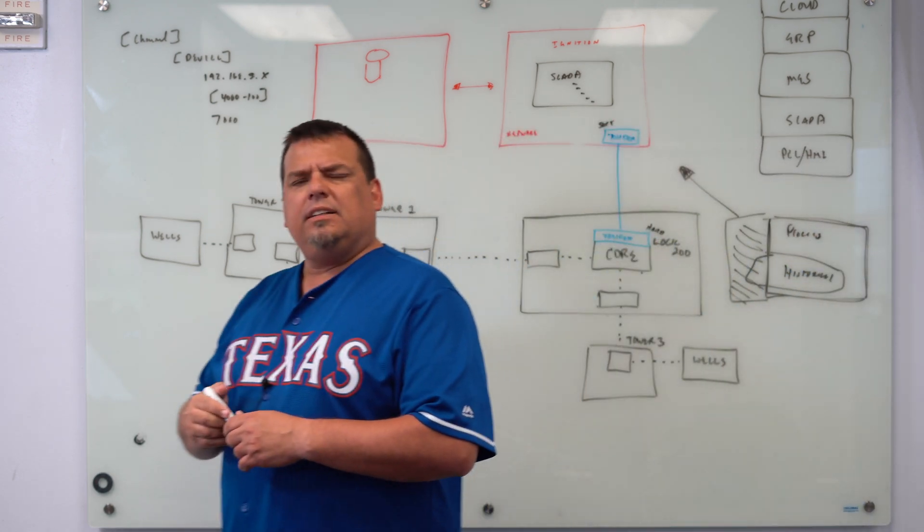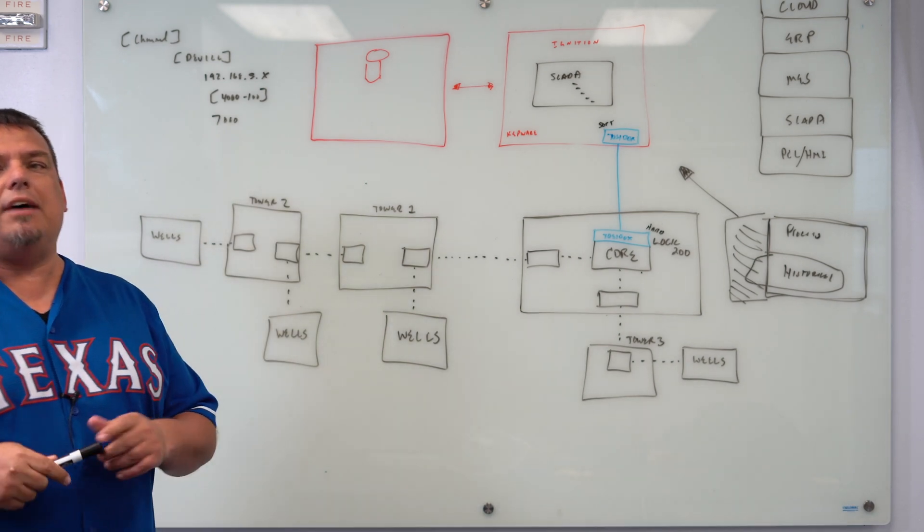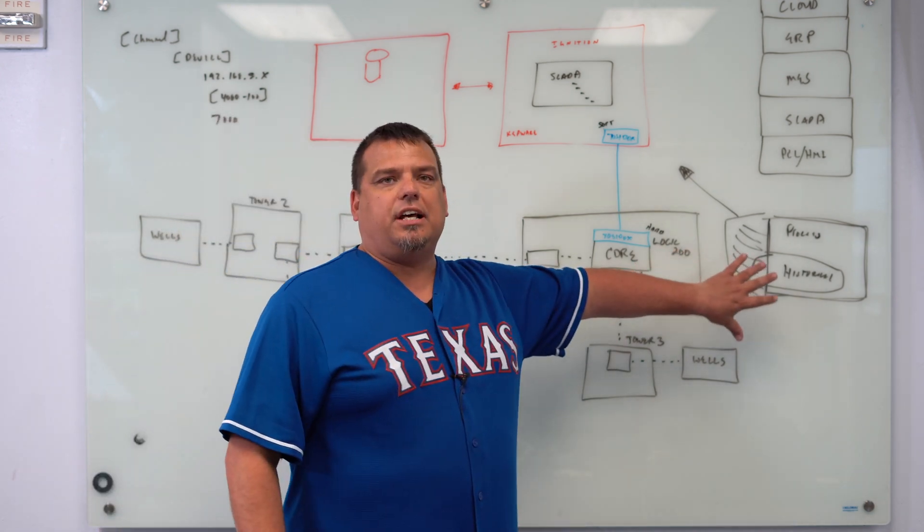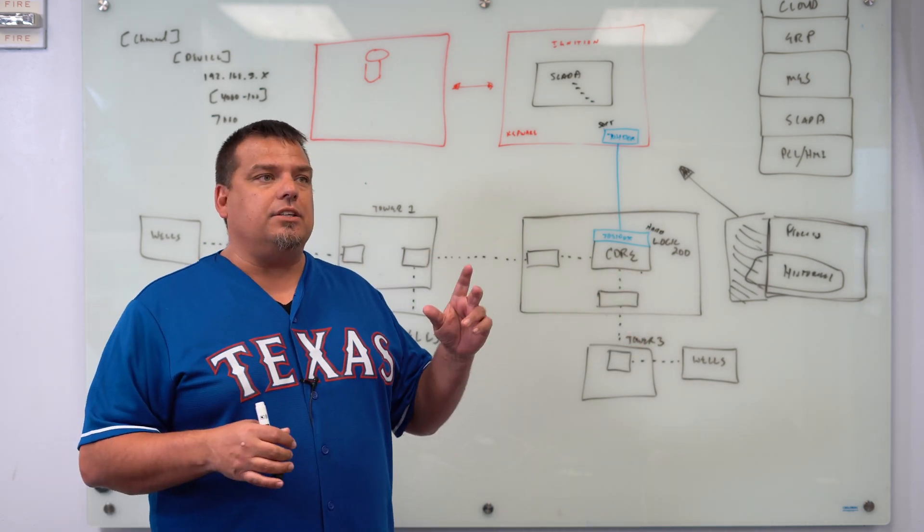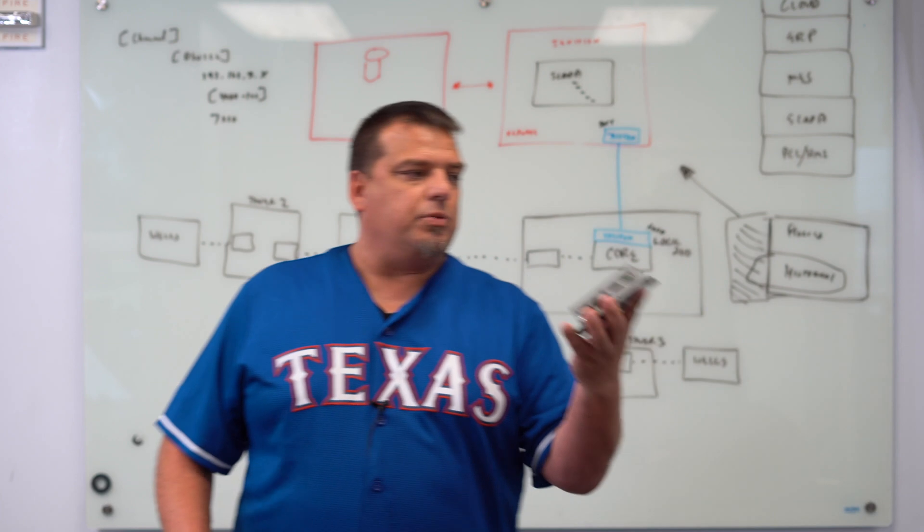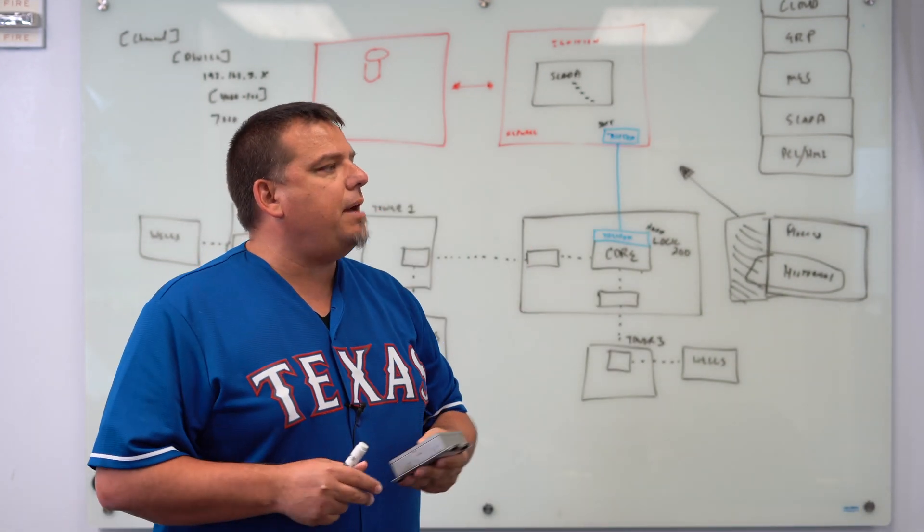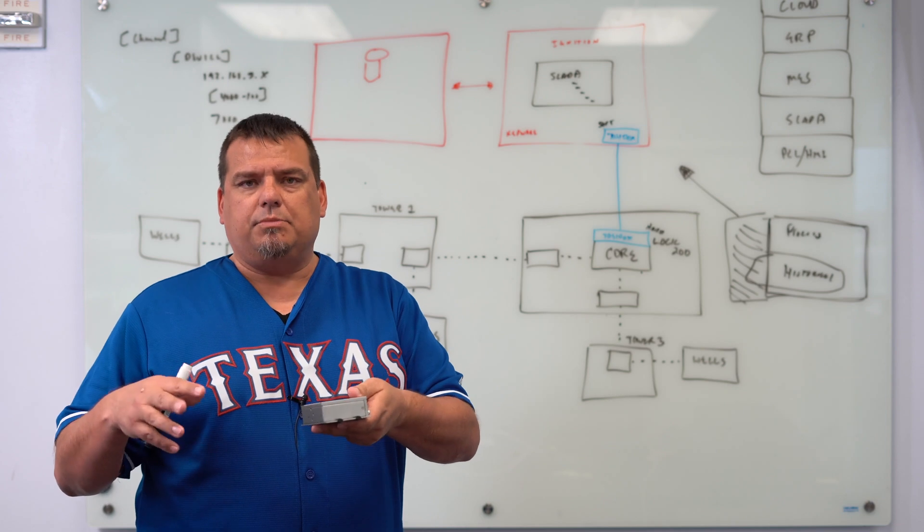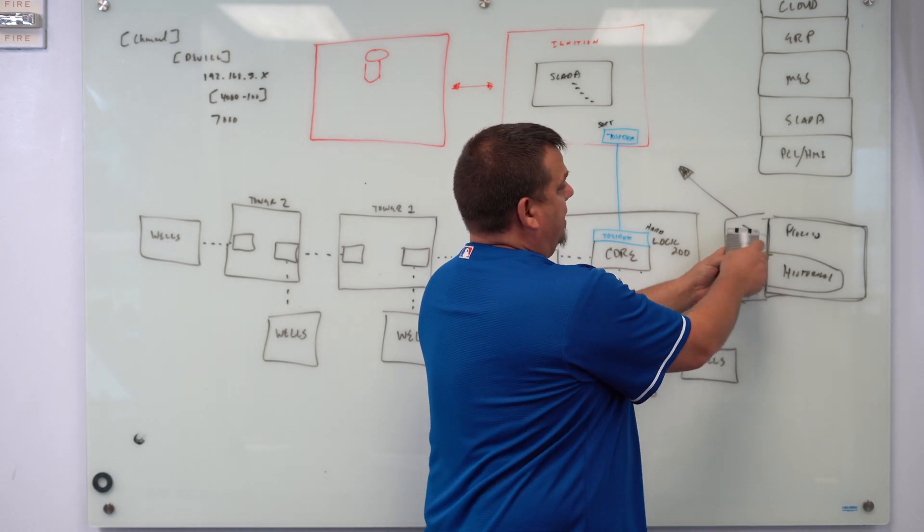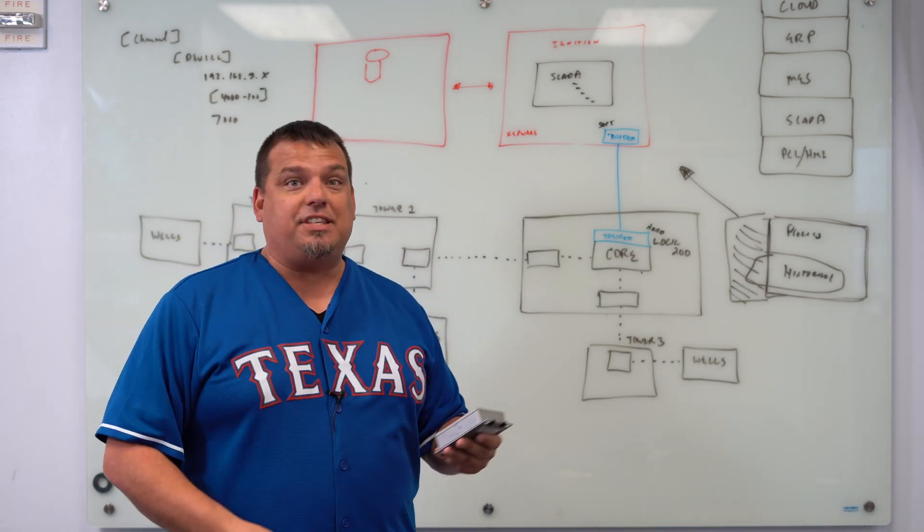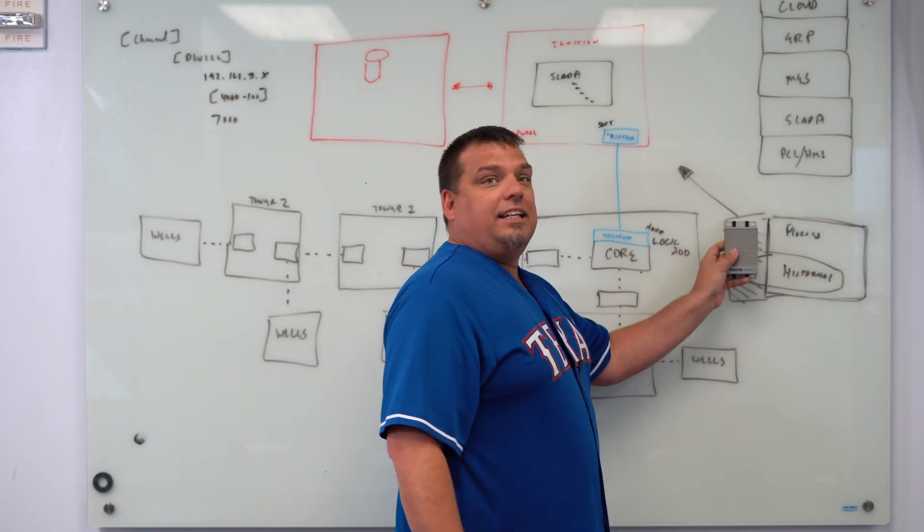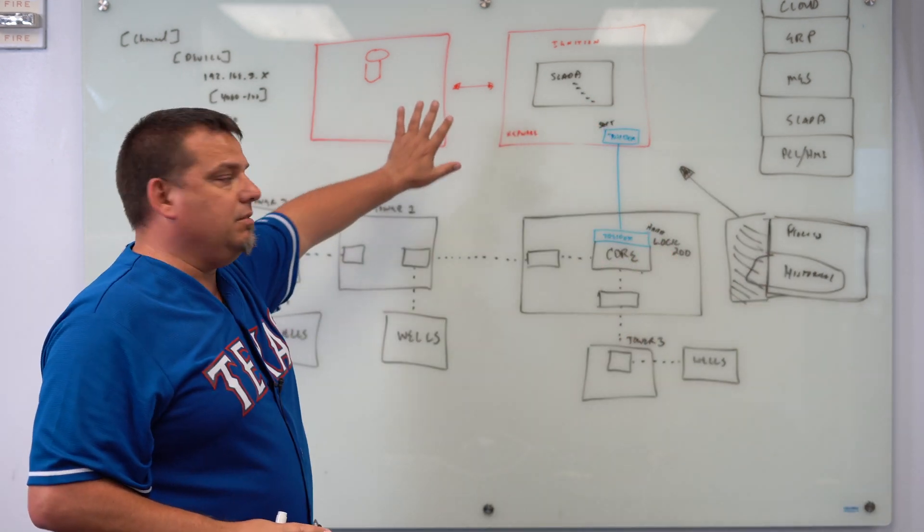Question, Zach? Is the edge device going to be a cellular gateway bypassing the existing wireless network? The beauty of MQTT is that we have a lot of options. The way that we generally put an edge device out in the field - right now we have an implementation down in San Antonio in a water application. The typical infrastructure we use for the edge gateway is we use an Advantech UNO, which runs $400 to $500 each. Then we use a PepLink Mini BR1 cellular modem, which costs like $280, and we put dual SIMs in there. For about $800, we can put an edge gateway out here that is able to collect all this information for us and point it up into our namespace. Going in the future, as they add wells, as they pop new wells - that's putting it into production - part of the installation of the ABB Total Flow is the edge gateway with that ABB Total Flow. Configure the node ID in here, point it to the broker, and everything shows up in the namespace.